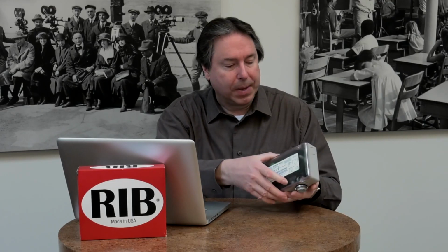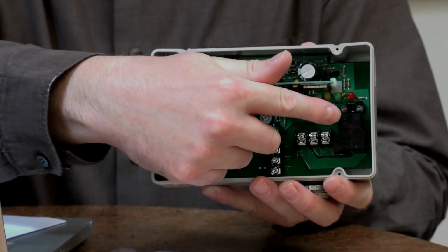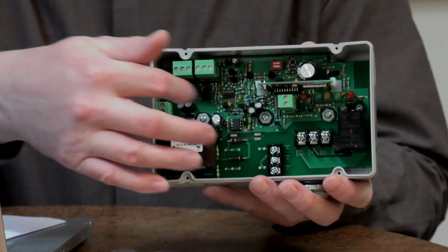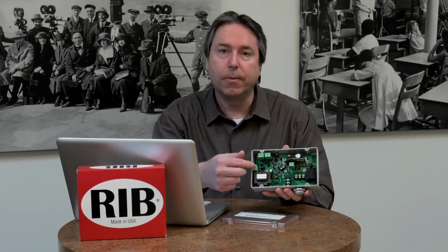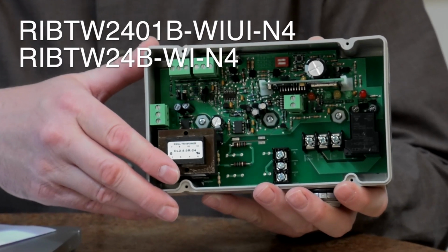Both of them have the discrete input, and the device that I happen to have here has two universal inputs. And just like with an automation controller, it allows you to do 0 to 5, 0 to 10 volts, 4 to 20 milliamps, dry contact, and also a 10K2 thermistor. Internally, here's your 30 amp relay. You can also power this with 24 volts or 120 volts, all off of the same two part numbers. Let me show you how it works.